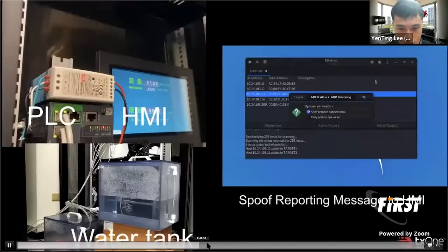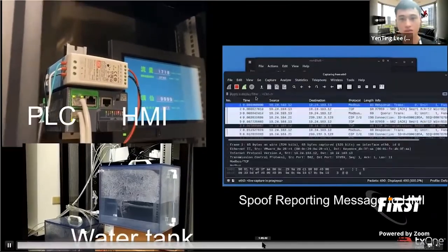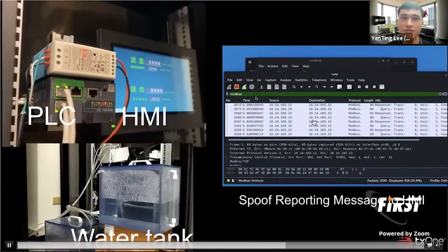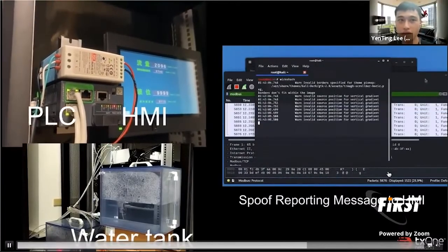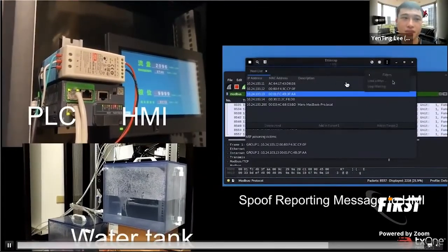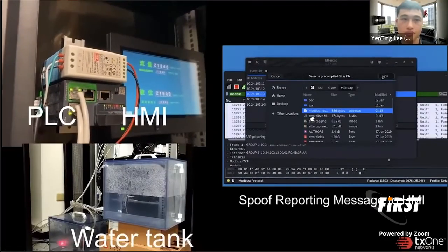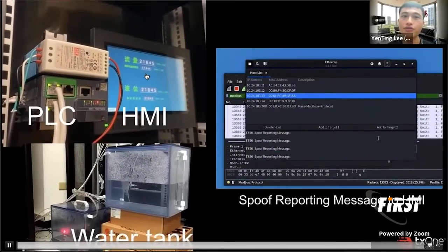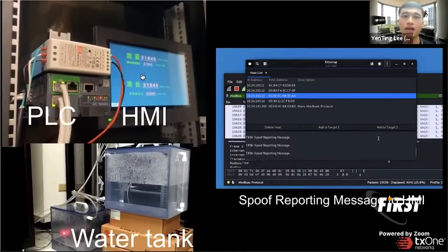Sorry, the video is okay. Let's pass. Then we successfully sniff the traffic between the PLC and HMI, and we try to upload spoofing traffic. Now we can see the HMI showing that the value is about 20 liters. This could easily cause an employee to make a harmful decision.